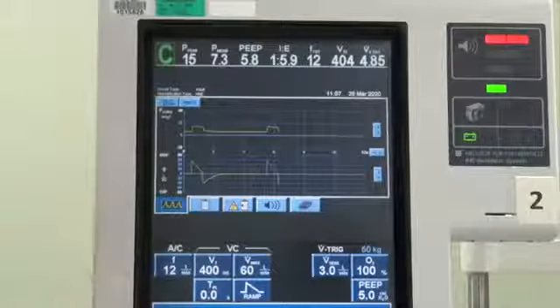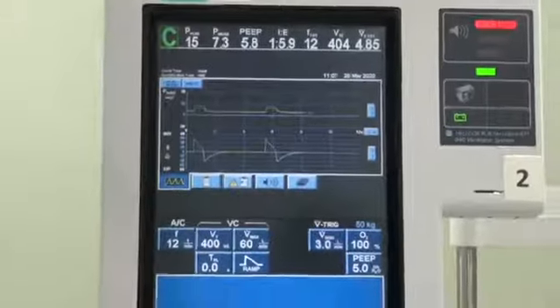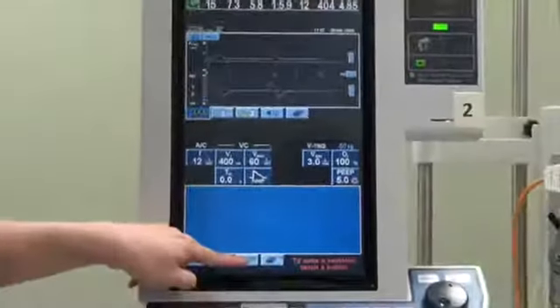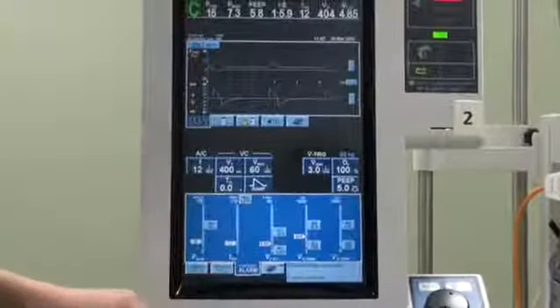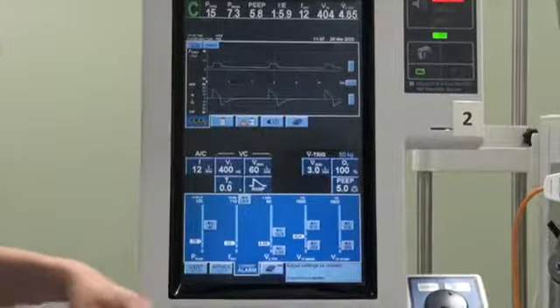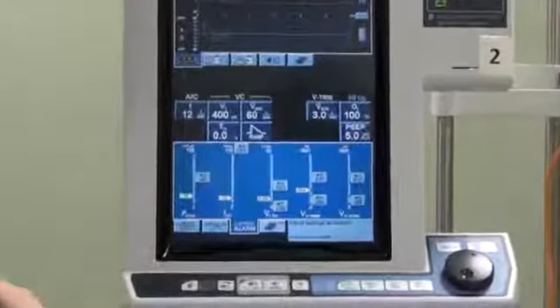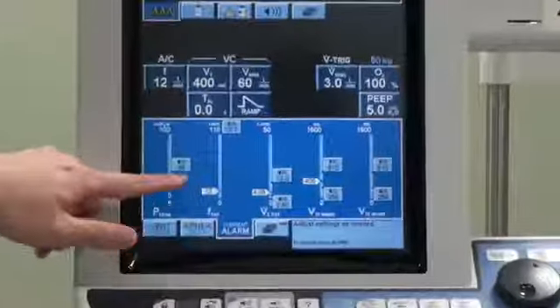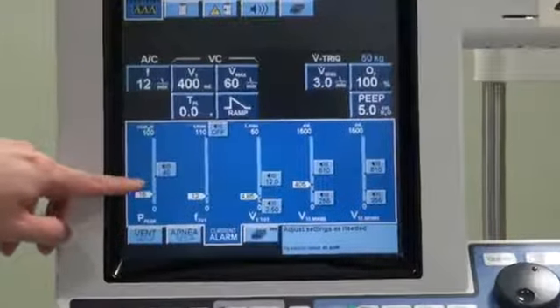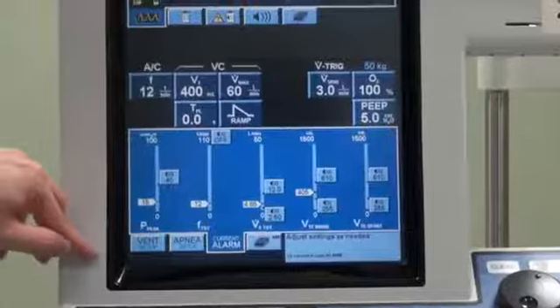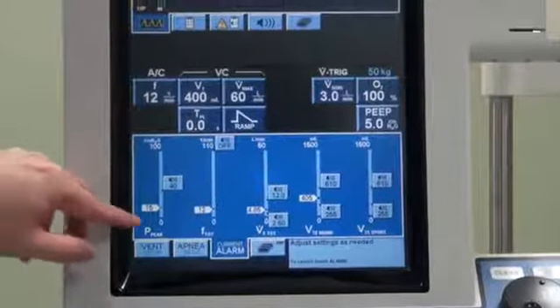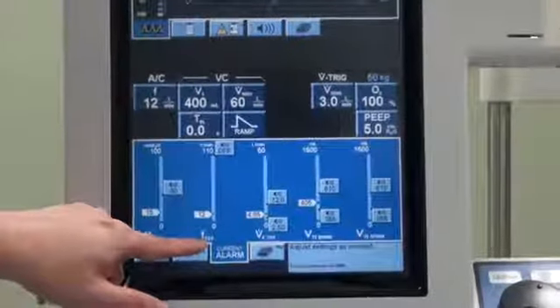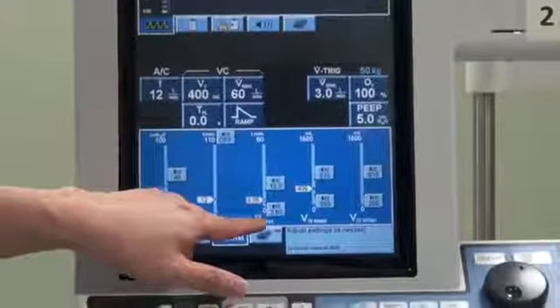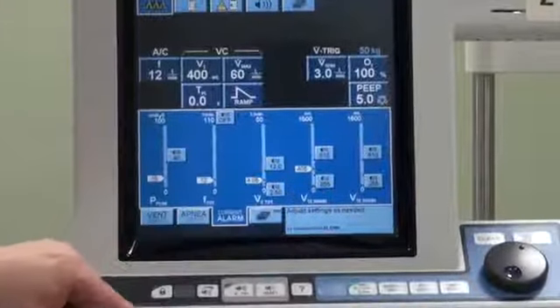Okay, once you have this set of values, the next thing that you want to set is the alarm setting. The alarm setting will allow you to be notified when the patient breathes beyond or below a certain safety limit. And when you press that button, you will see a pop-up screen which allows you to set the alarm for the peak airway pressure, frequency, the minute ventilation, and the tidal volume.